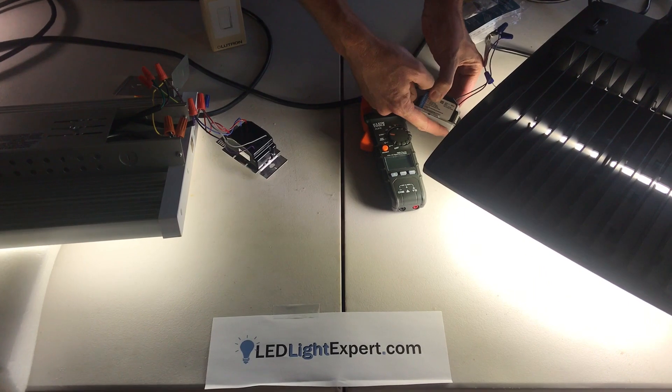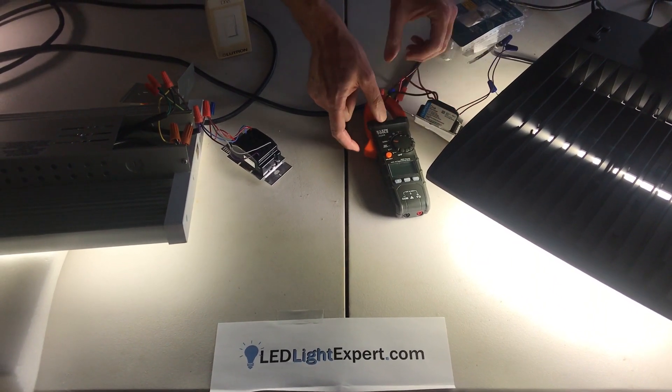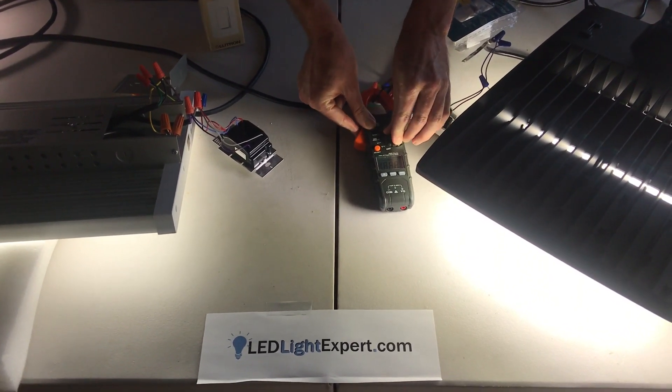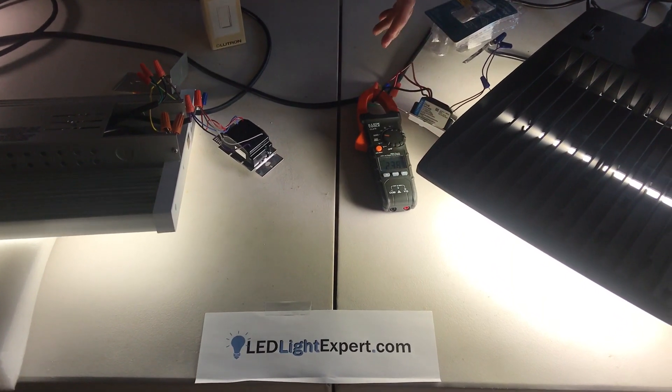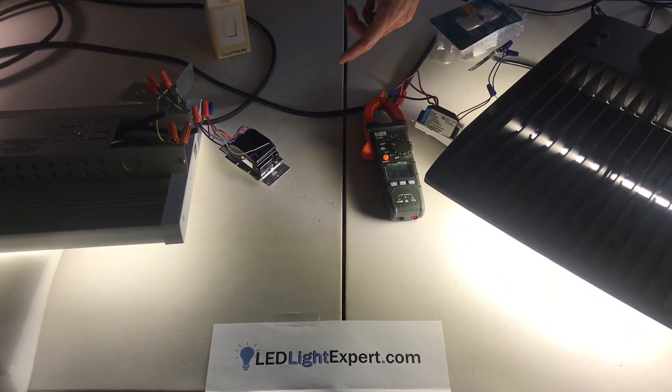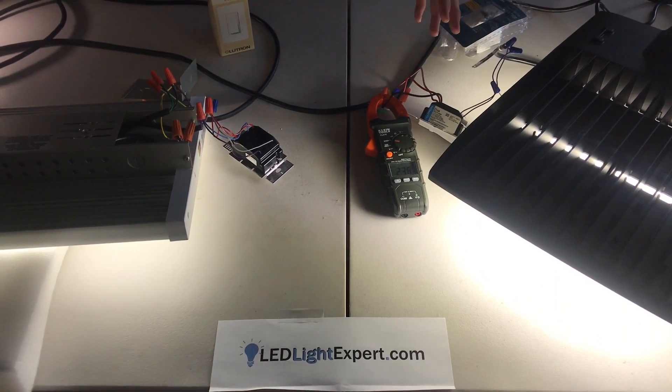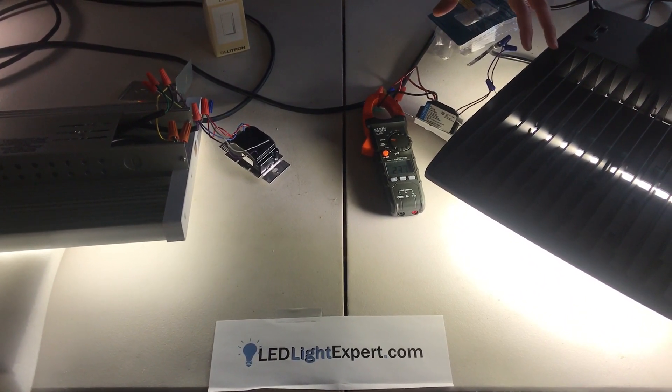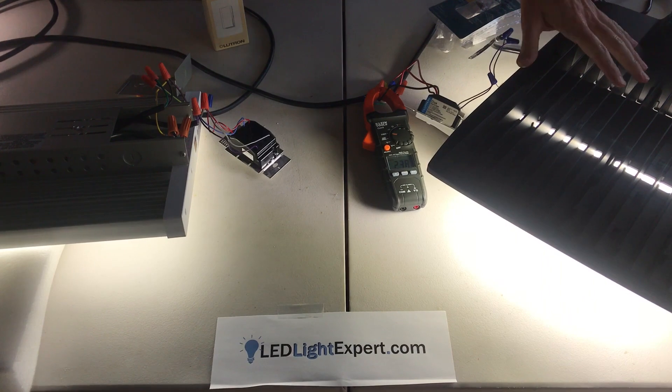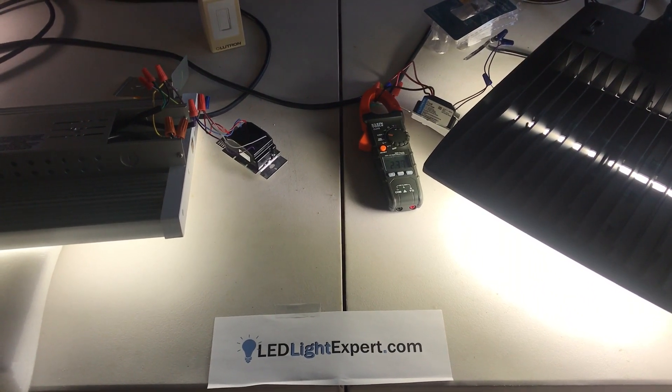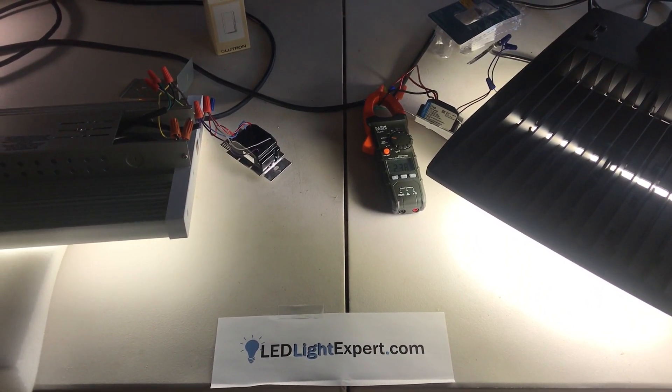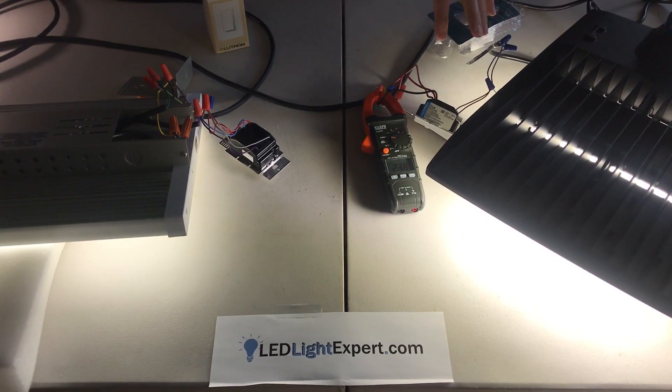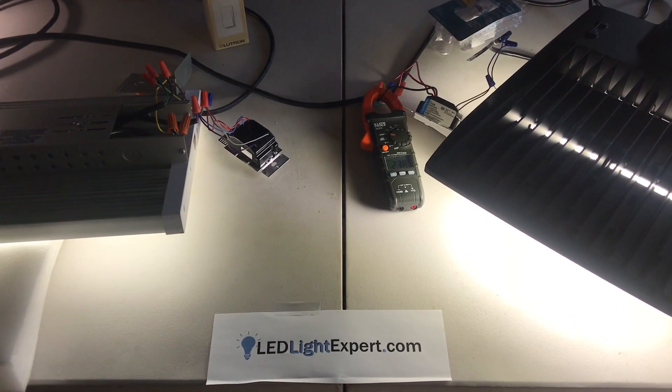Now over here I do have my clamp meter on. You can see we're drawing a full 2.4 amps. I've got about 125 volts here, so that'll be right on with a 300 watt unit. Remember that amps is watts over volts. So running 208, 277, whatever we have will change that number.